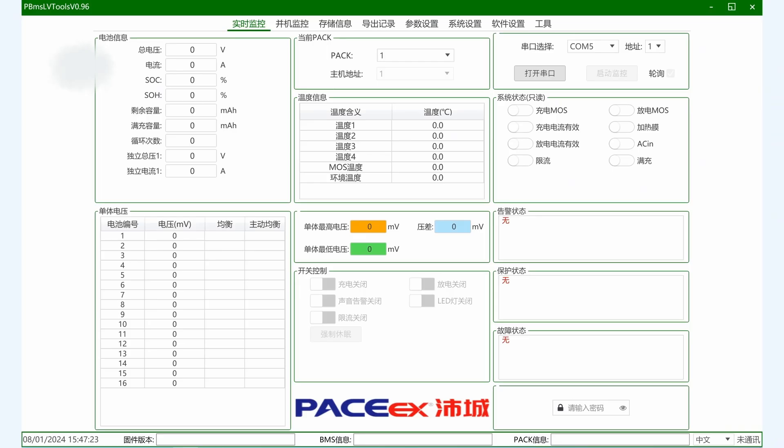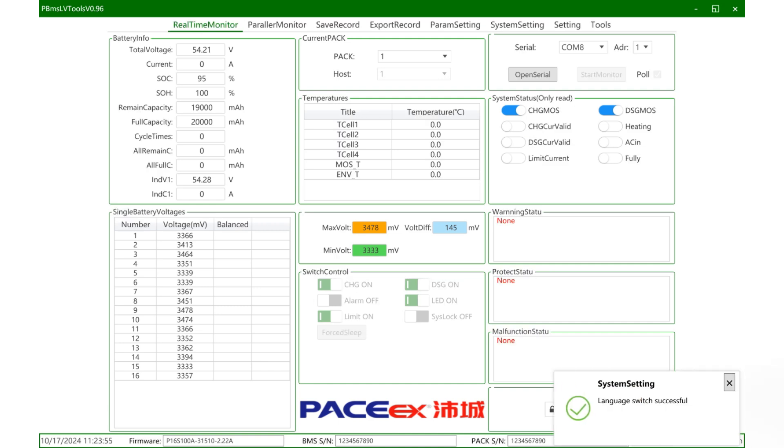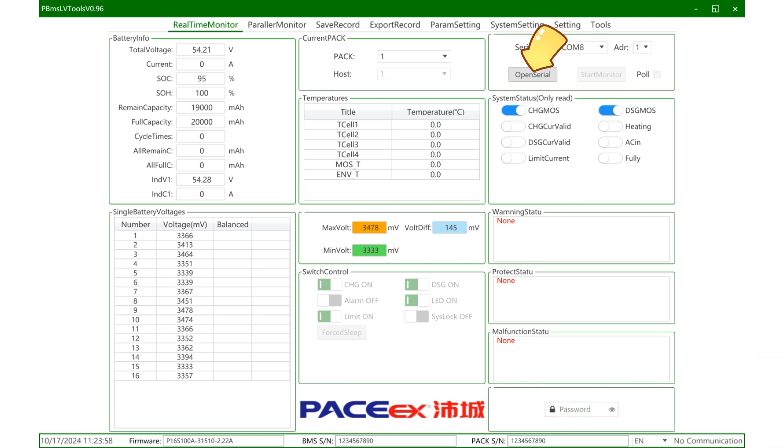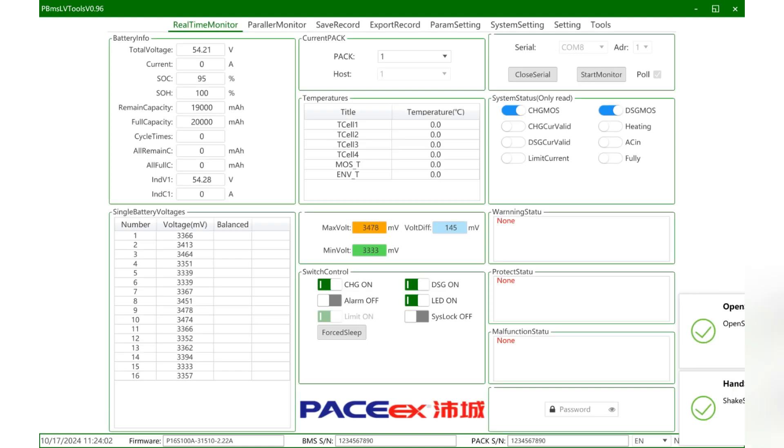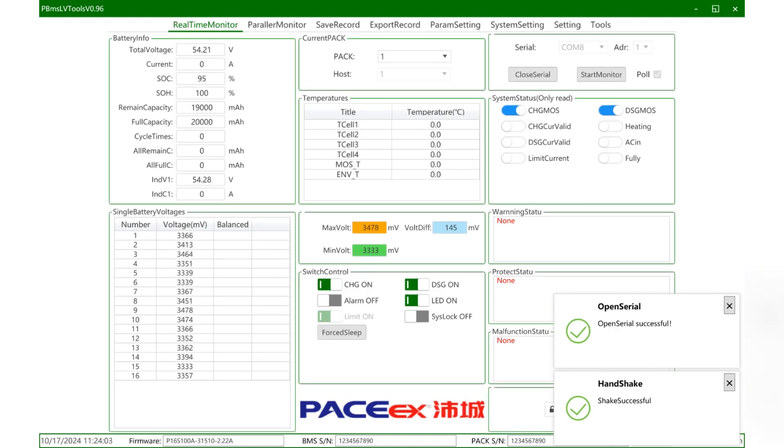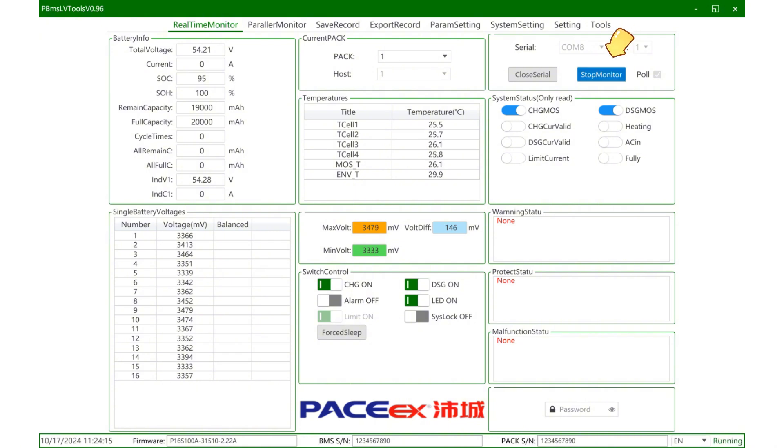First, look at the real-time monitoring function. If it is in parallel, you can click this polling method. When multiple units are used in parallel, we can pull the information of each BMS and pack by address. Click to start monitoring. You can see all BMS data here. When using a single unit, you can turn off polling.